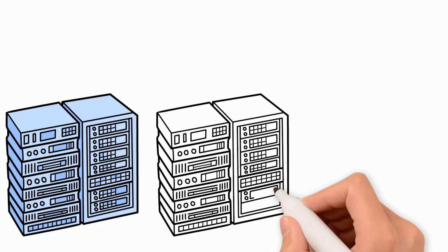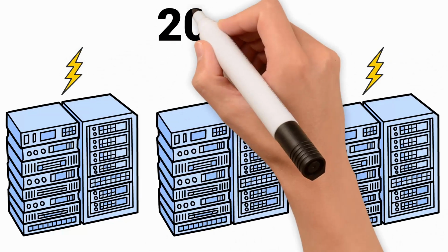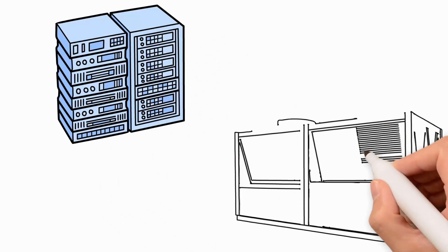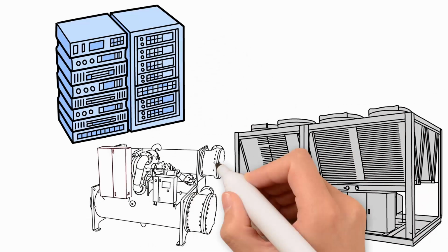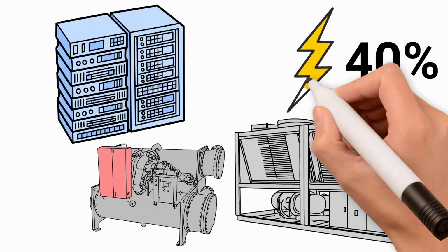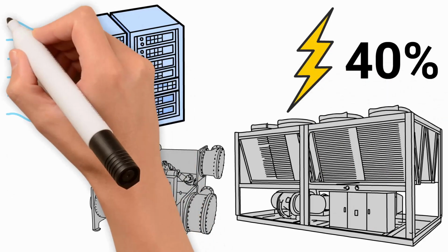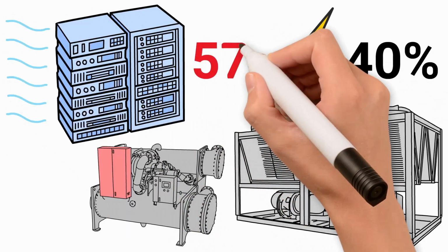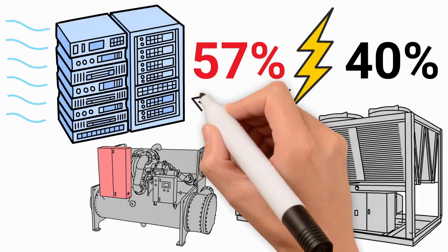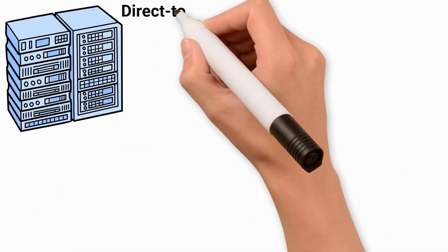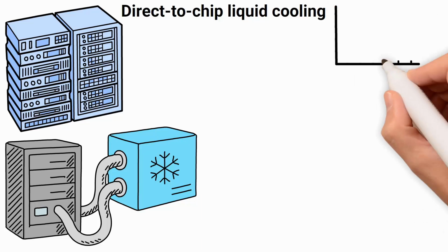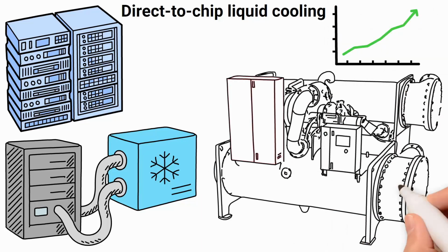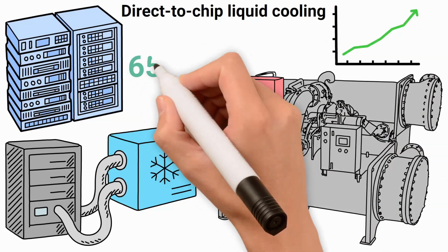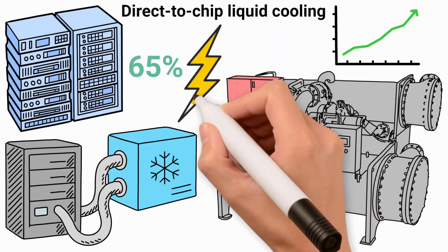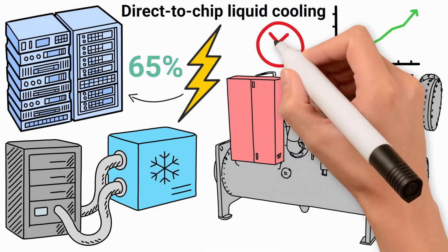Let's look at three identical data centers, each receiving 20 megawatts of power. The first relies on traditional air cooling with chillers and compressors. Nearly 40% of the power is tied up in cooling. The result? Only about 57% of capacity goes to compute. The second adopts direct-to-chip liquid cooling. It's an improvement, but compressors are still in play. Compute climbs to about 65% of available power. Better, but still not enough.